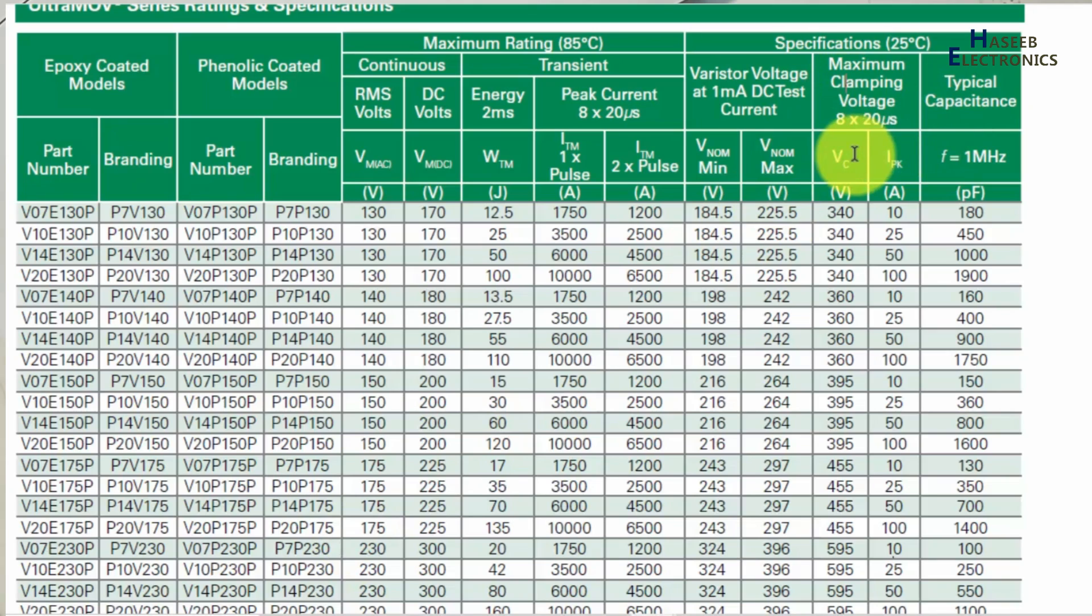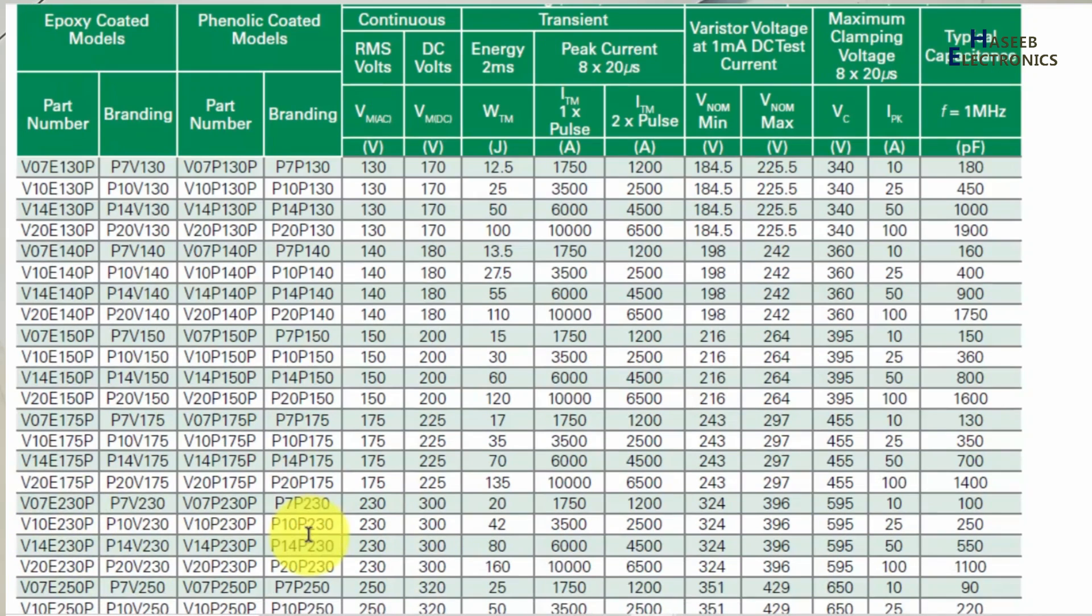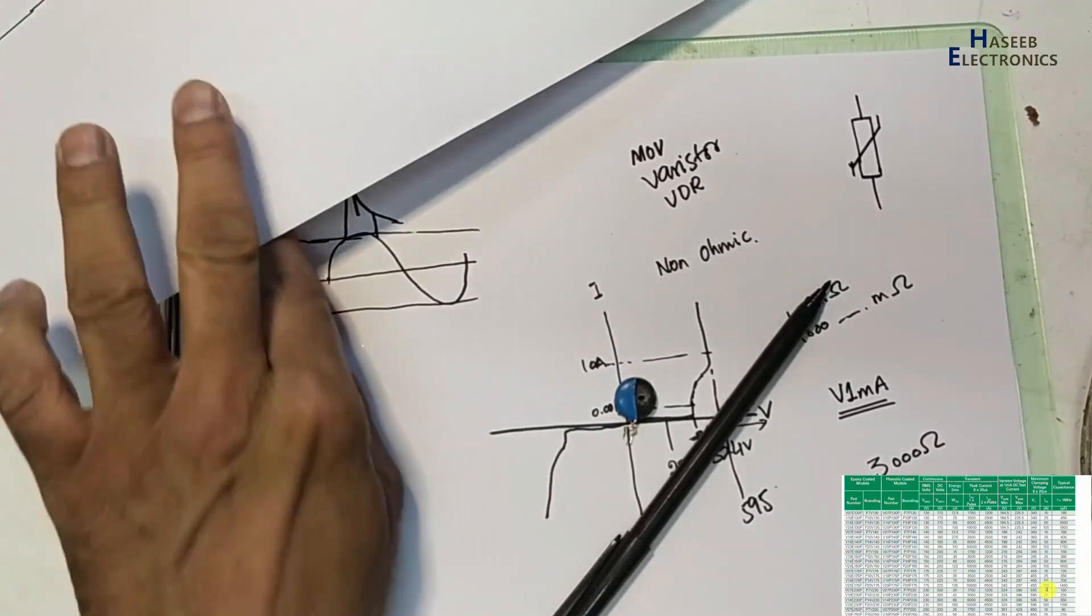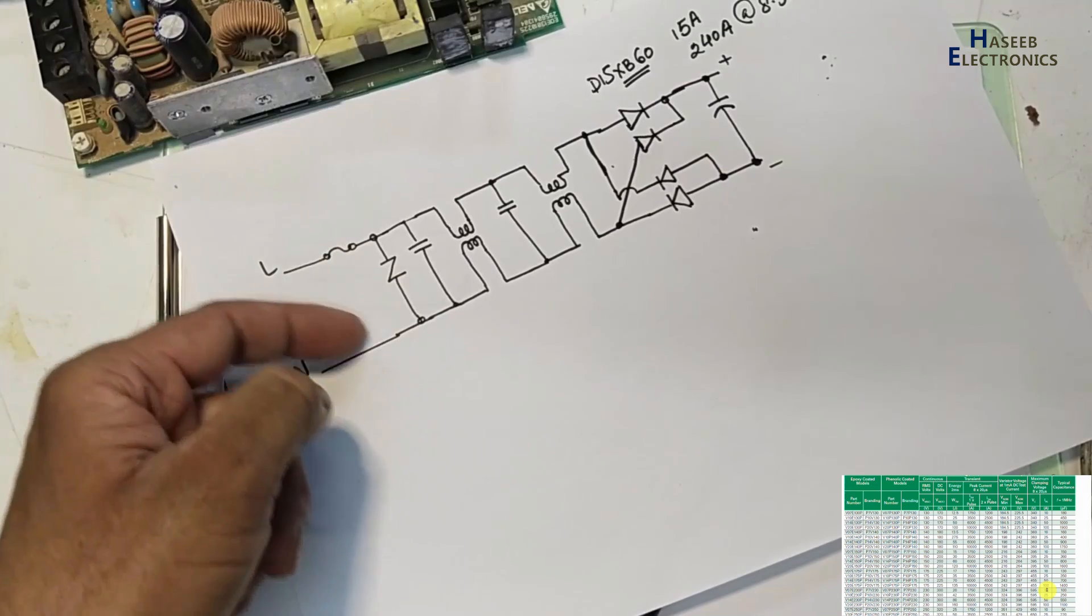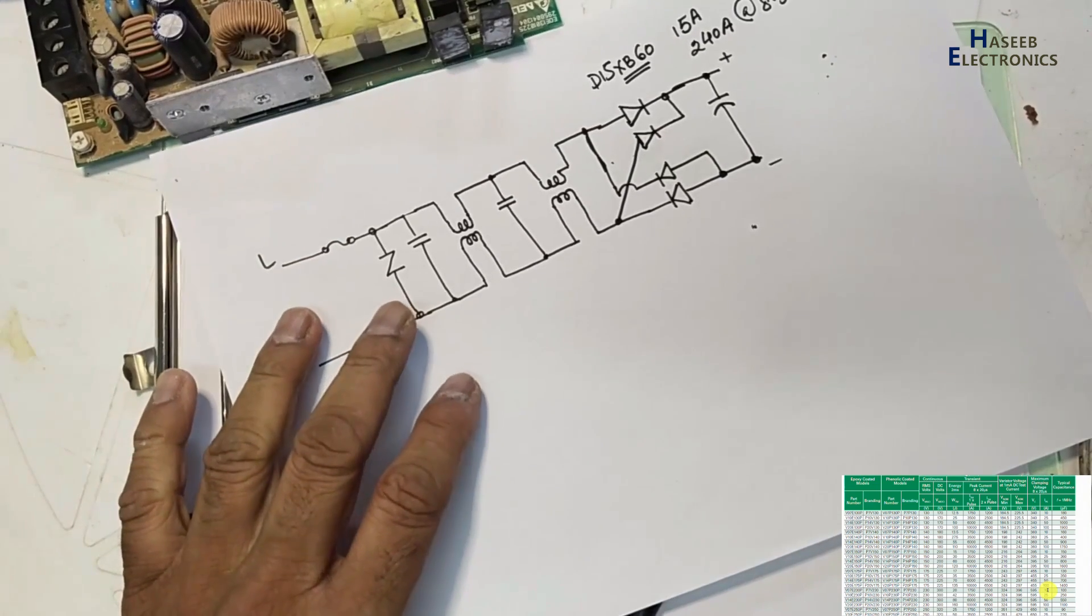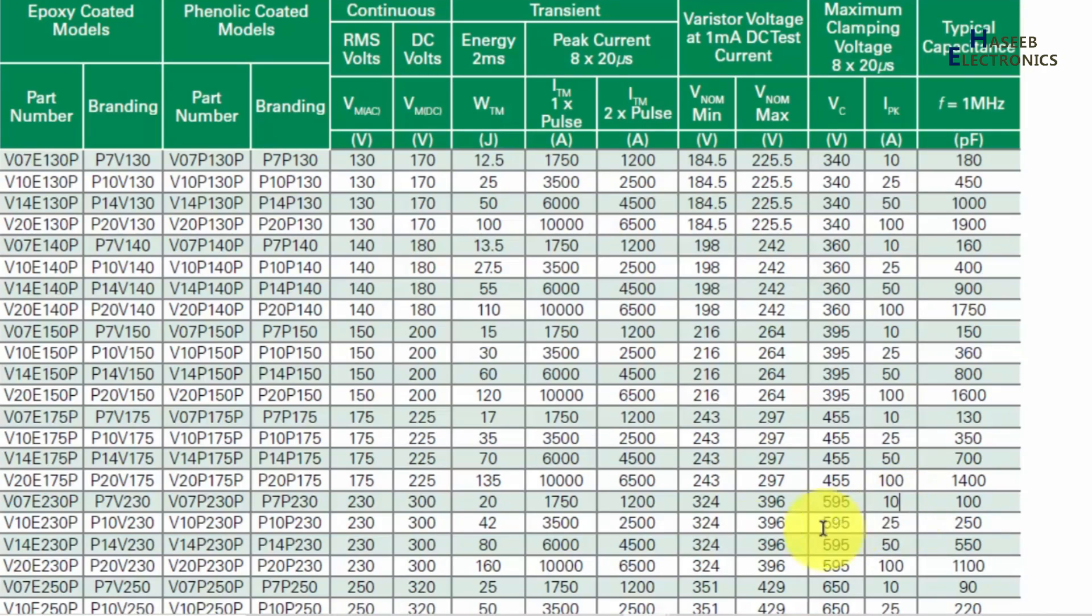Then maximum clamping voltage - that is also 8 by 20 microsecond pulses. When the voltage increases, if we see this disk size, that is 7 - V07E230P - it will clamp voltage at 595 with 10 ampere current in this path.